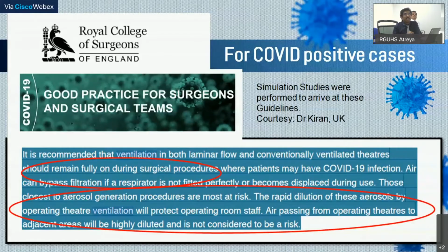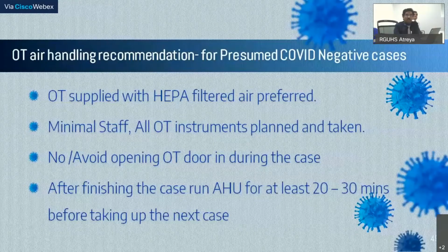So it's better to use an OT with HEPA filtered air, minimal staff, and all OT instruments should be planned and taken inside beforehand. Do not open, or avoid opening, the OT door during the case. After finishing the case, run the AHU for at least 20 to 30 minutes before taking up the next case so that dilution removes all infectious particles.